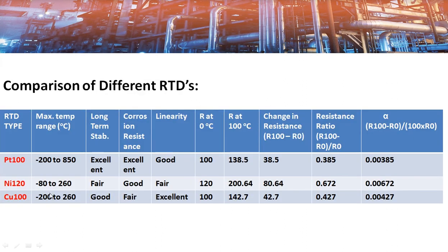Here you can see the comparison of different RTDs. Three RTDs are compared with respect to three metals: PT100, Nickel 120, and Copper 100. The number in the sensor name indicates the resistance at 0°C — for example, platinum 100 has 100 ohms at 0°C, and nickel 120 has 120 ohms at 0°C. Platinum sensors have the highest temperature range and best long-term stability, followed by copper and then nickel. Corrosion resistance is best for platinum, then nickel, then copper.